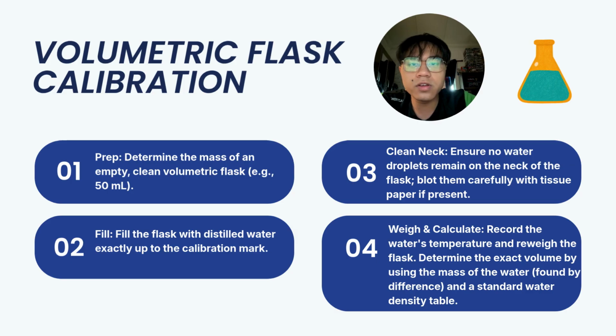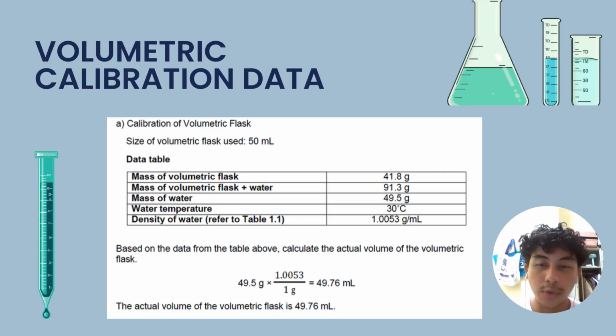Celsius. Volumetric flask calibration. Firstly, the preparation. We determine the mass of an empty clean volumetric flask, for example, 50 milliliter. Secondly, the fill. We fill the flask with distilled water exactly up to the calibration mark. Next, we clean it. Clean the neck to ensure no water droplets remain on the neck of the flask. Blot them carefully with tissue paper if present. And lastly, weigh and calculate. Record the water's temperature and reweigh the flask. Determine the exact volume by using the mass of the water, which is found by difference, and the standard water density table. And this is another of our sample data for volumetric calibration. So as you can see, the final actual volume of the volumetric flask after overall calculation is 49.76 milliliter.